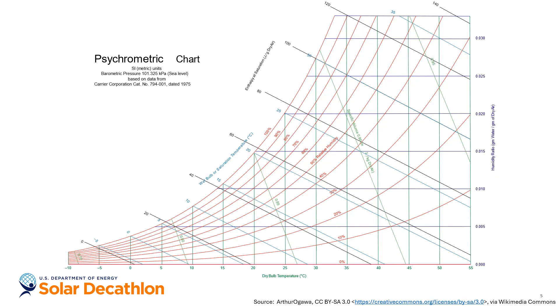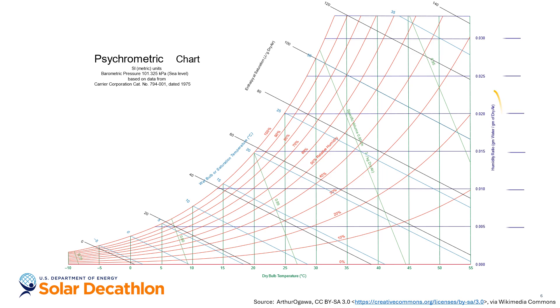Now back to the chart. There are a few key terms we need to define. First is the dry bulb temperature, shown horizontally on the x-axis and indicated by vertical green lines. Dry bulb temperature refers to the ambient air temperature without any influence of moisture or wind speed. This is the temperature measurement done by most thermometers and thermostats.